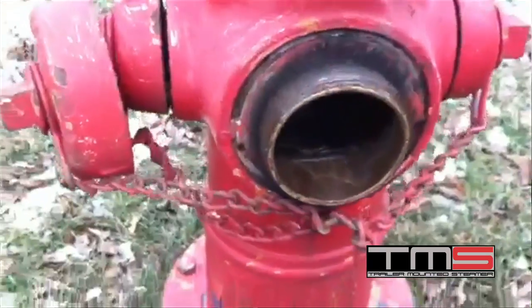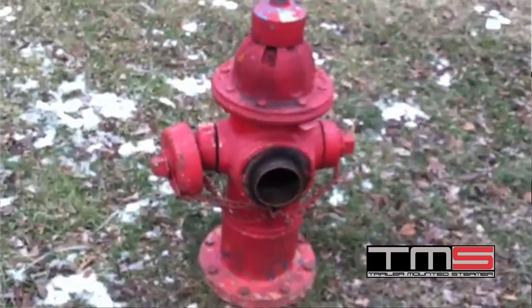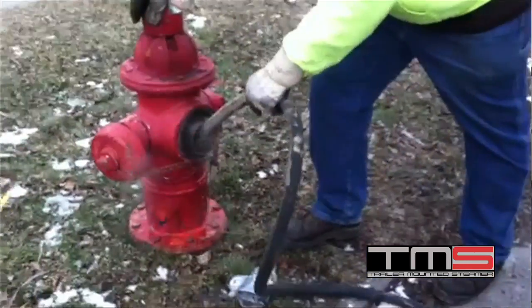Simple things and my years of experience have been built into this with a lot of different knowledge and expertise. The TMS is a self-contained thawing machine developed for municipal water maintenance during months of inclement weather. We got started with this project because the city water department in Buffalo, New York needed a better way to service their aging water system. As hydrants get older, some of them lose their ability to drain water after use. If the hydrant is not dewatered, it may freeze as temperatures drop. When a hydrant freezes, it is not possible for fire companies to use that hydrant. Our system thaws the ice so that the hydrant can be dewatered and put back in service in a few minutes. There are two TMS units being used in the Buffalo system and have been every winter for the last seven years.